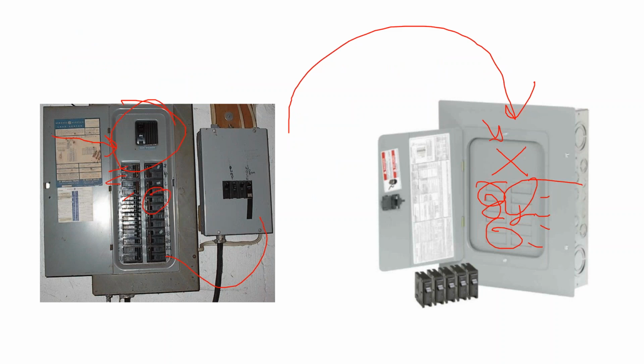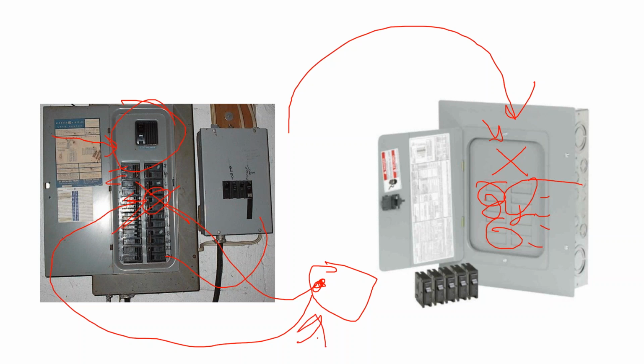So if you're running to a generator or a solar inverter that has its own internal disconnect switch, the intent is that you have an external switch that can kill the power at that point so that you can service the equipment. If you kill the power inside the equipment, then you still have this hot lead coming in to the equipment, and that's not particularly safe.